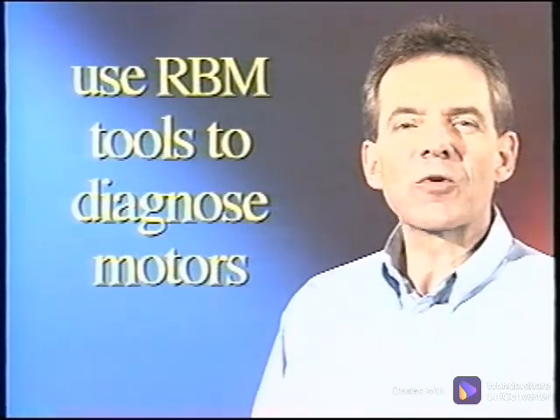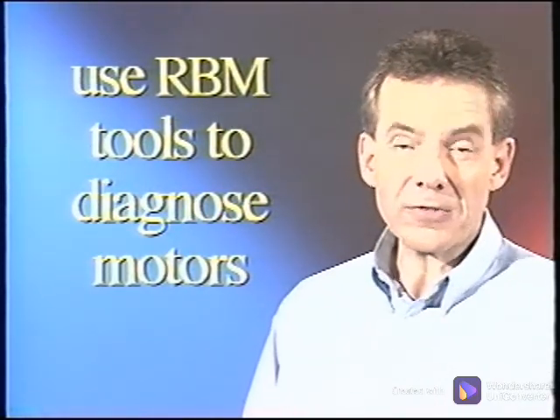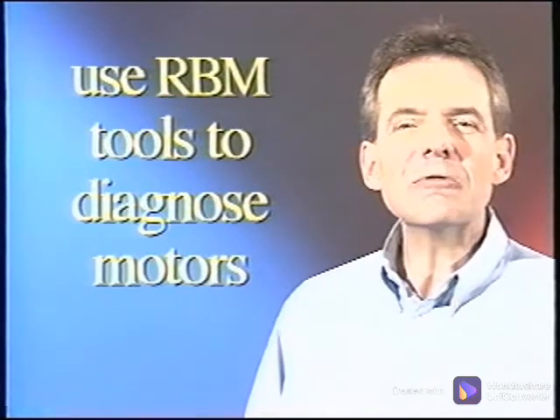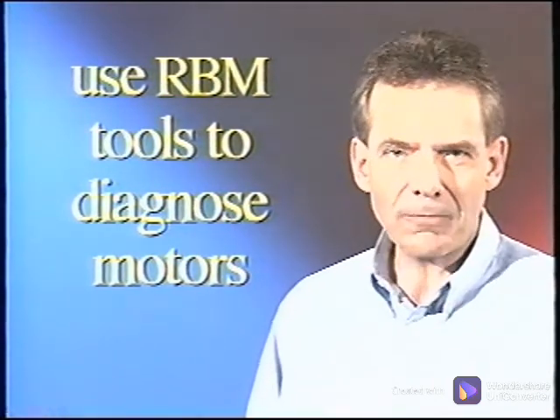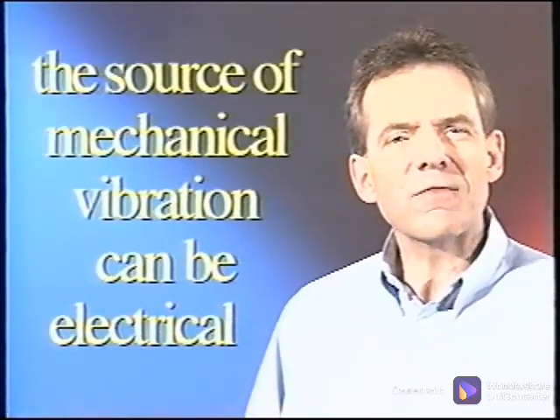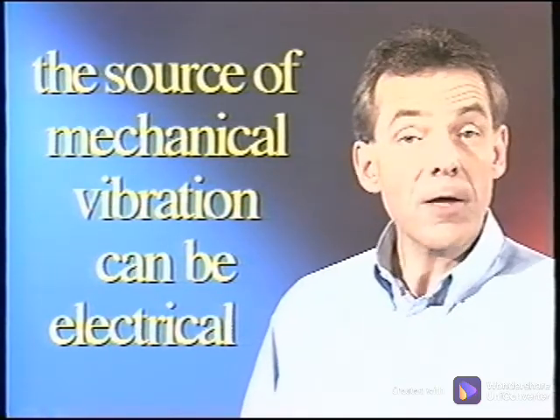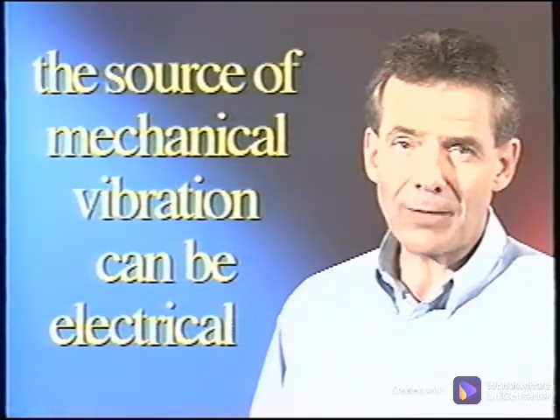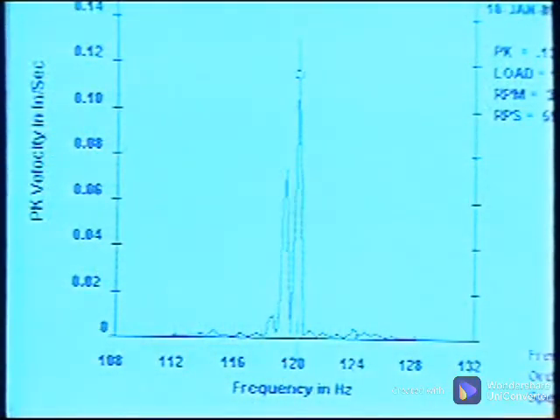The RBM tools for diagnosing AC induction motors can be at your disposal. Use them to help determine the source of the problems. Remember, the source of a machine's mechanical vibration may be caused by an electrical problem. Use high-resolution vibration measurements to differentiate between line frequency multiples and running speed multiples. The high resolution also separates the slip frequency sidebands.